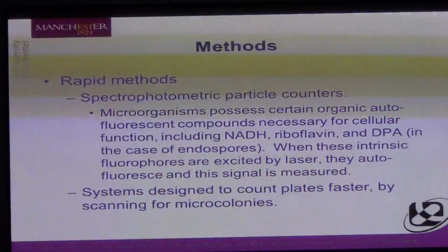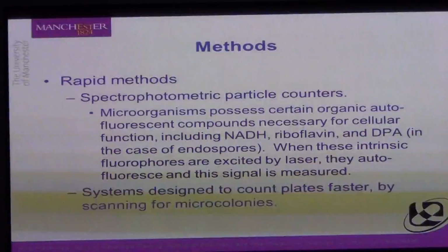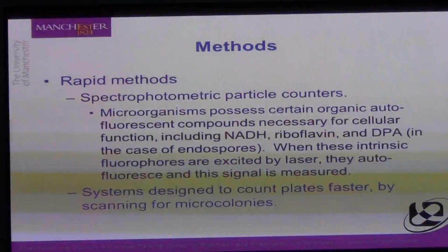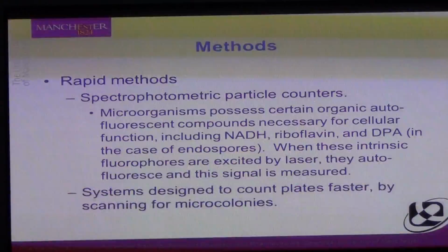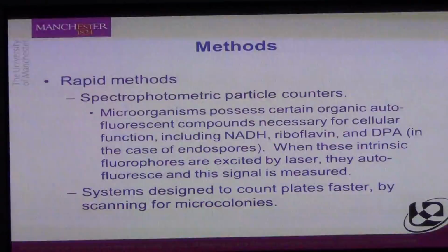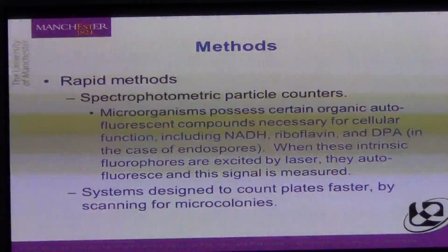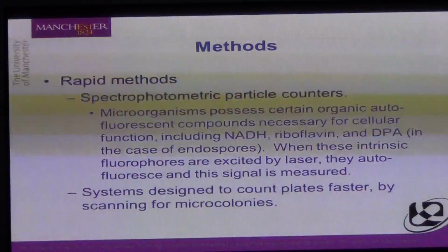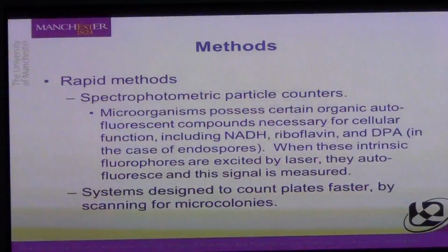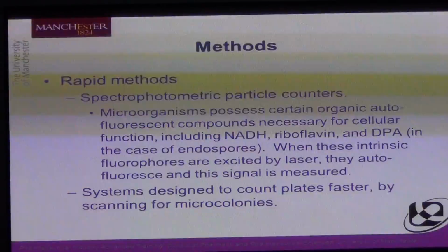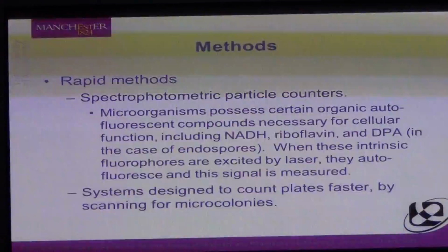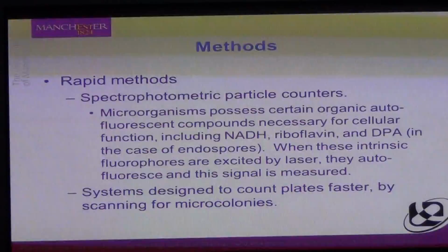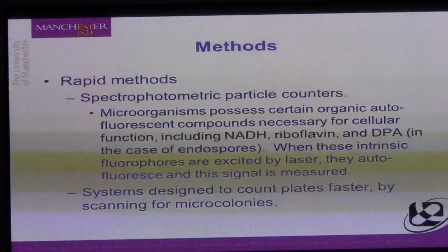So they tell us there's something there, but they're less good at telling us how much and what it was. Also, it's important to stress at the moment this technology is somewhat in its infancy, and some of the counters are prone to fluoresce to certain fibres that might be shed from cleanroom suits, or even to alcohol sprays. I think they will become the future one day, but at the moment they're useful, but they cannot replace the classic methods.